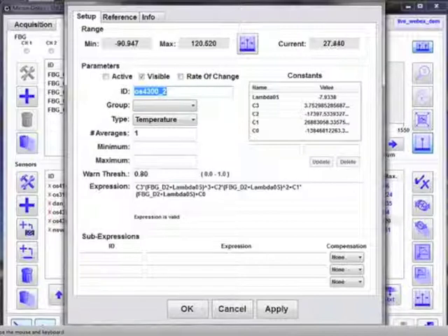There's quite a bit to averaging in ENLIGHT because you have to realize the implications of the method that you choose, and the implications based upon the instrument that you have. So on an SM125, as Todd mentioned, you can average the spectral response, which is improving the source of the data that's being used to do a software peak detection. However, when you average the full spectrum, you are averaging every peak within your system on that channel, or actually on all channels with the spectral averaging.